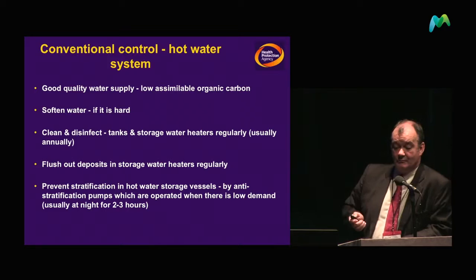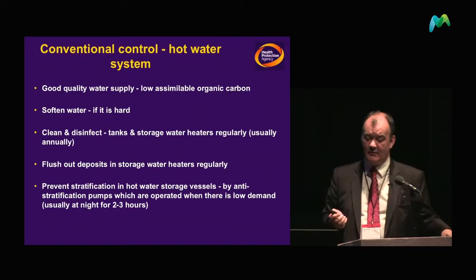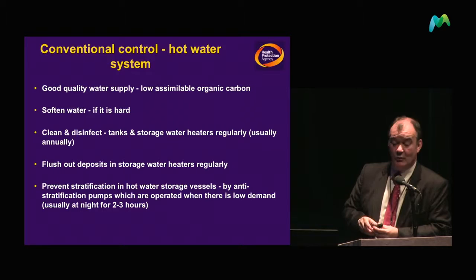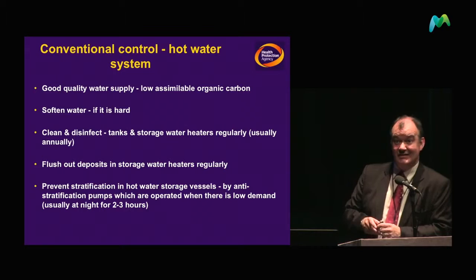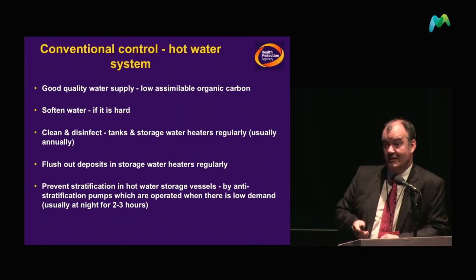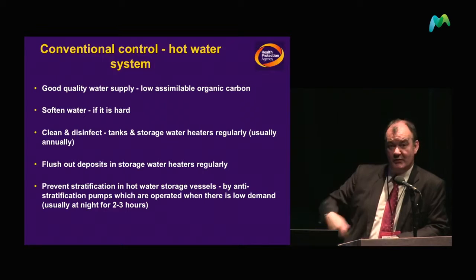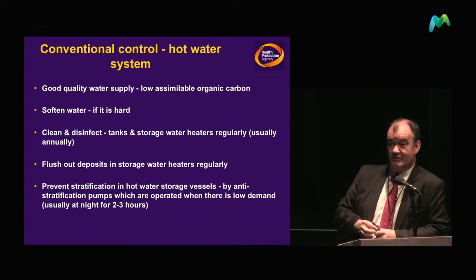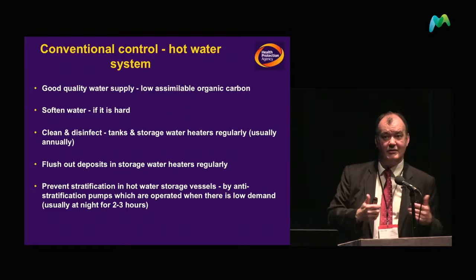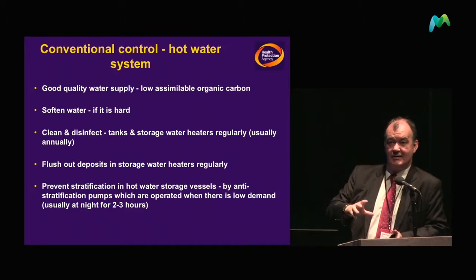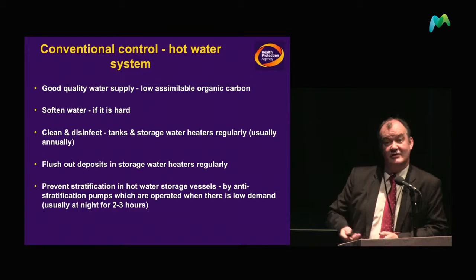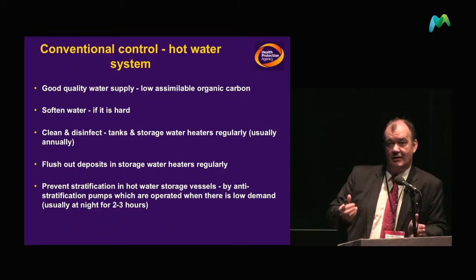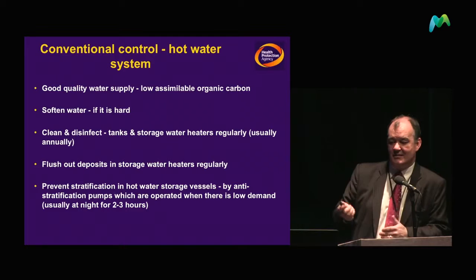In terms of hot water systems, we try to ensure the quality of the water is good, that it is soft water, and we clean and disinfect any tanks, removing any deposits that appear quickly. One important factor is water storage itself — if you have a storage capacity that holds water for a month you've got a real problem, as that is an ideal location for Legionella to grow. Increasingly we're seeing smaller tanks being produced so hospitals may only hold one or two days' worth of water.